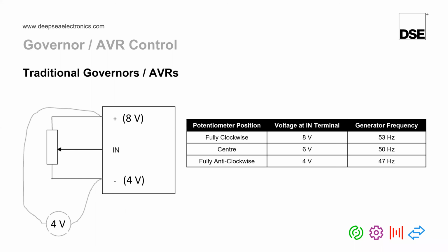So we'll start by looking at a very traditional governor or AVR and have a look at the wiring. So very typically on a governor or AVR, it will have 3 terminals on it, as can be seen on the slide on the left-hand side here. And these 3 terminals is where you would normally connect a variable resistor, a potentiometer. Some governors and some AVRs may have 3 terminals, some may only have 2 terminals. The operating principle between the 3 terminal and 2 terminal governor or AVR is exactly the same.